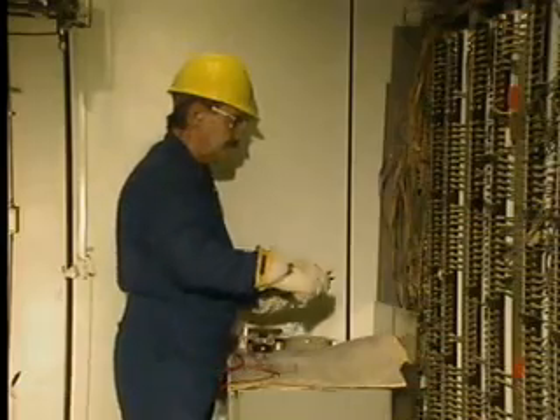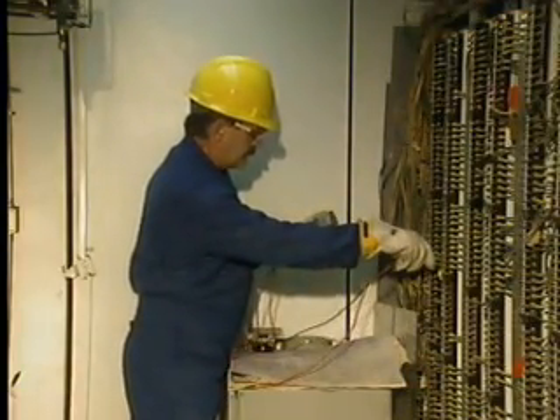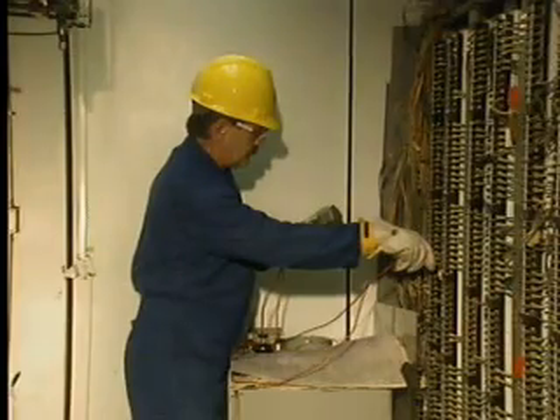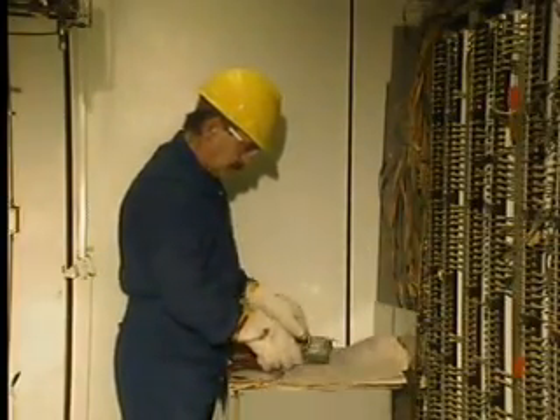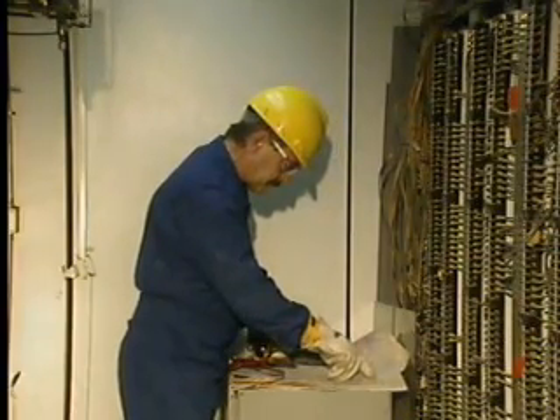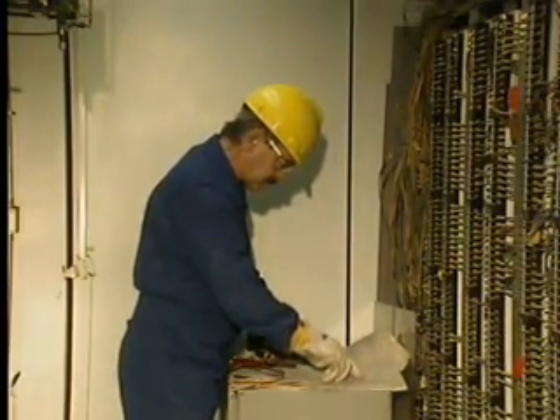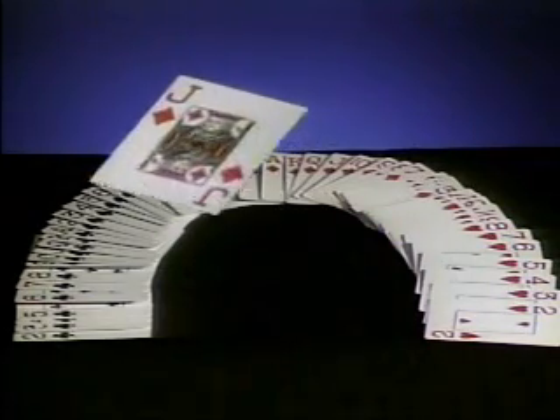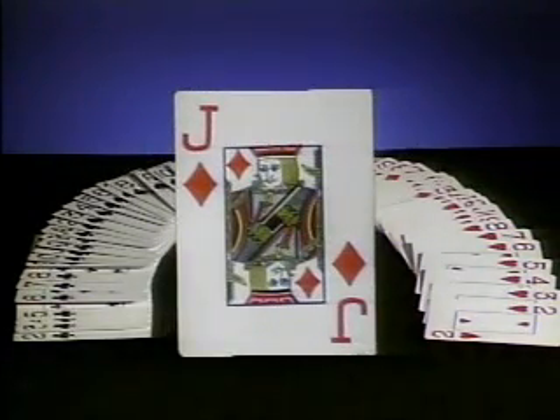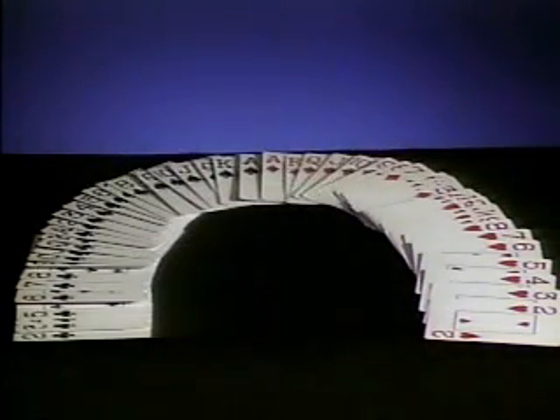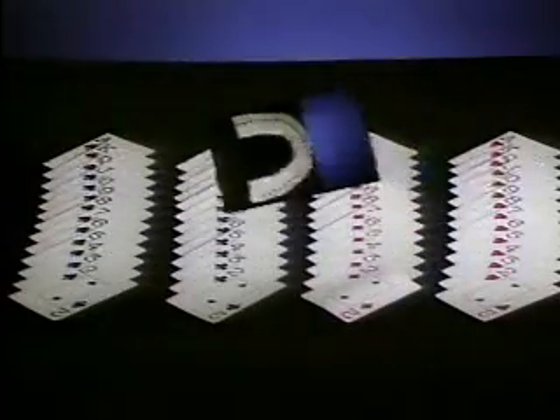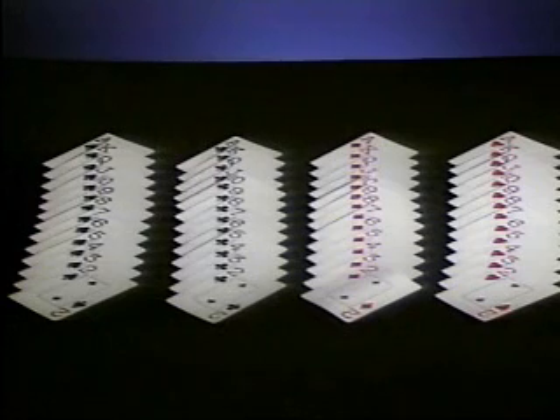In some cases, you can eliminate possible causes of a problem very quickly by using a method called half-splitting. This method involves splitting a circuit in half and reduces the remaining number of possible causes of the problem by half. Assume that someone has picked a card from a deck and we have to guess what it is. The task of identifying the card begins with 52 possibilities. Using the serial method to identify the card could take as many as 51 guesses. However, with the half-splitting method, the maximum number of guesses is reduced to 6. Each question or test eliminates half of the remaining possibilities until only one is left.